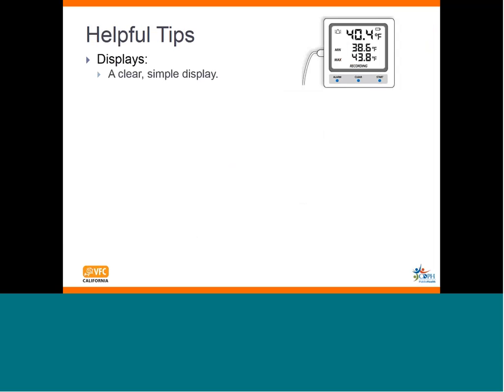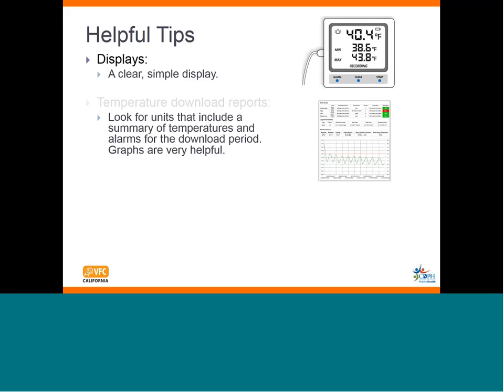From discussions and lessons learned from using digital data loggers, we found these helpful tips will ease implementing digital data loggers into your practice. A clear, simple display will make your twice-daily readings a simple task. Avoid loggers that use confusing symbols or icons and those with small, hard-to-read displays. Temperature downloaded reports: some units may only include basic data download reports containing hundreds of readings without a detailed summary report. Look for units that include a summary of temperatures and alarms for the download period. Graphs are very helpful.